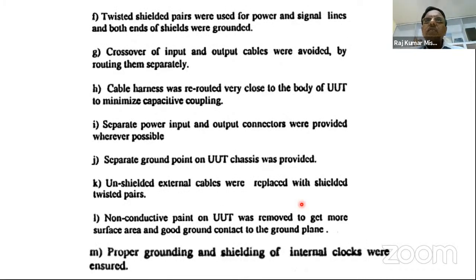Twisted shielded pairs are used for power and signal lines, and both ends of the shields were grounded. Very important point: crossover of input and output cables was avoided by routing them separately. Cable harnesses were routed very close to the body of the EUT to minimize capacitive coupling. Separate power input and output connectors were provided wherever possible, and a separate ground point on the EUT chassis was provided.